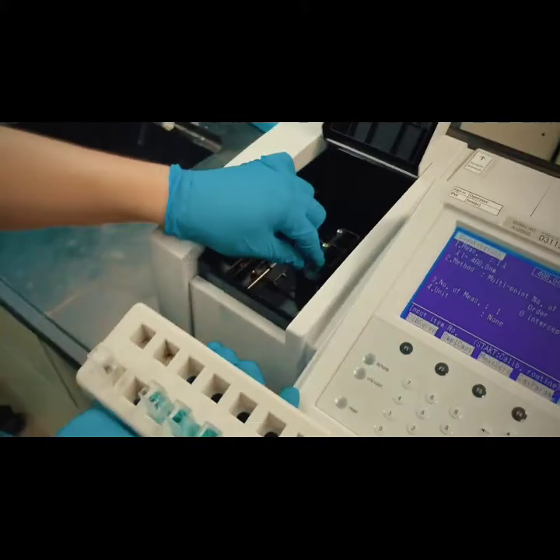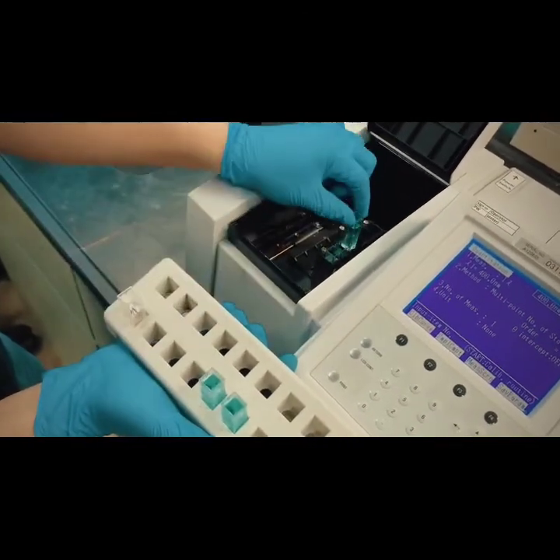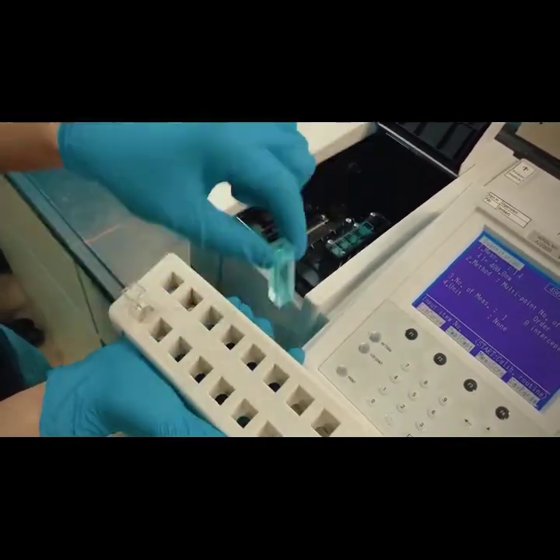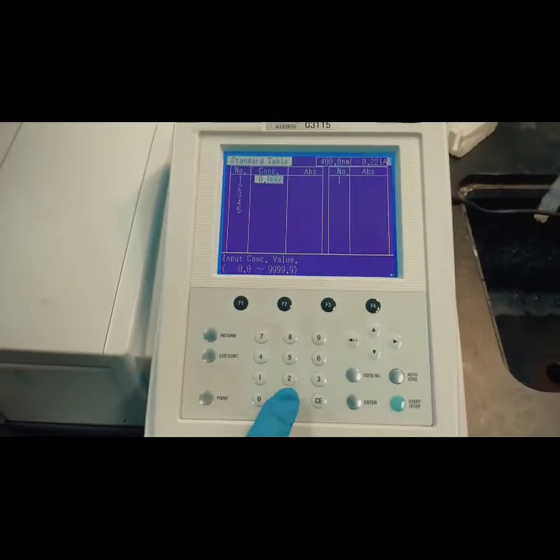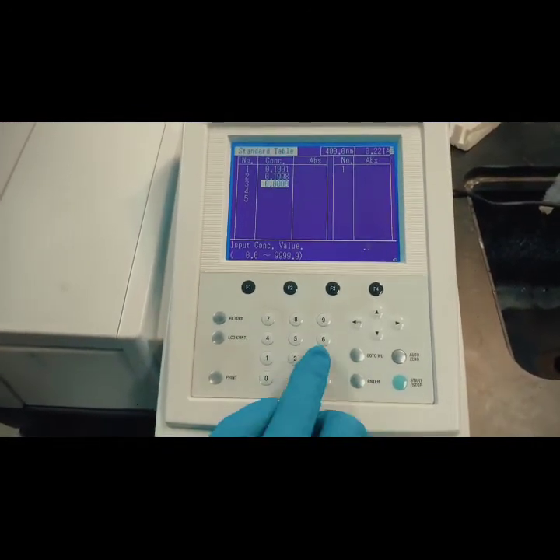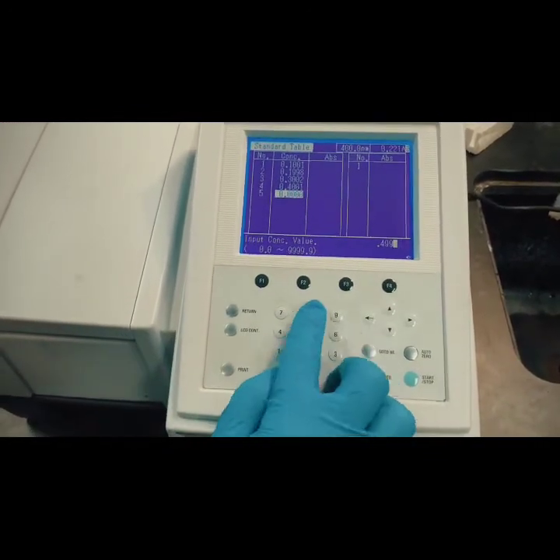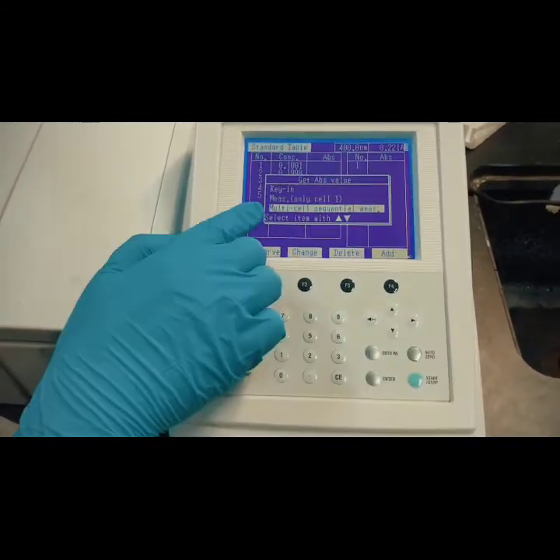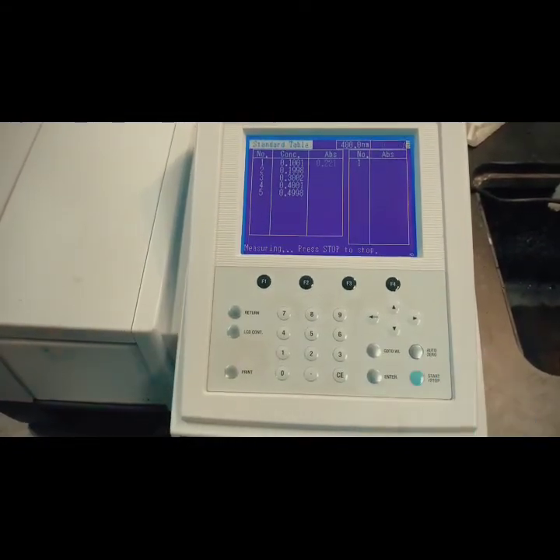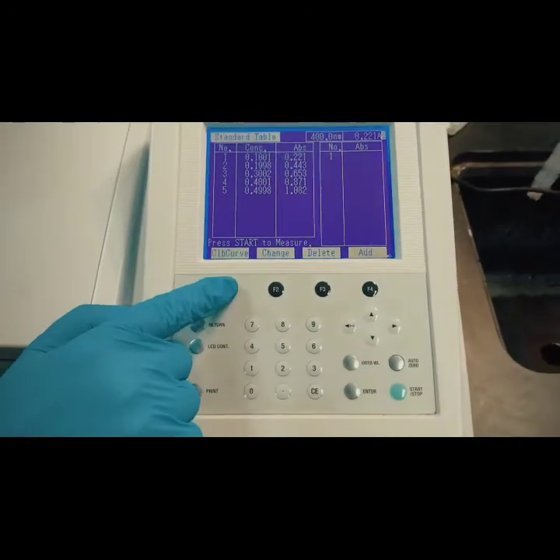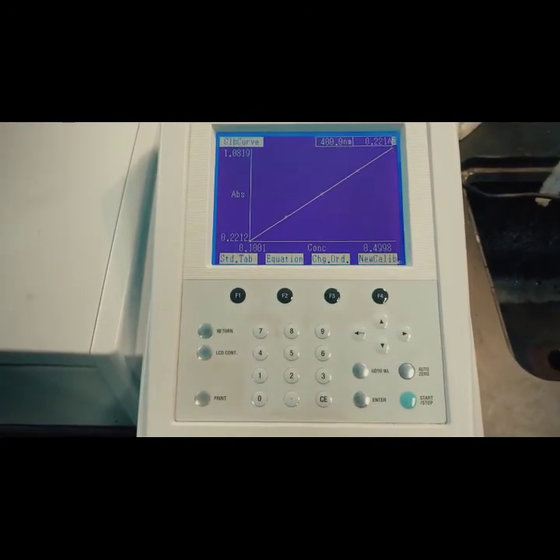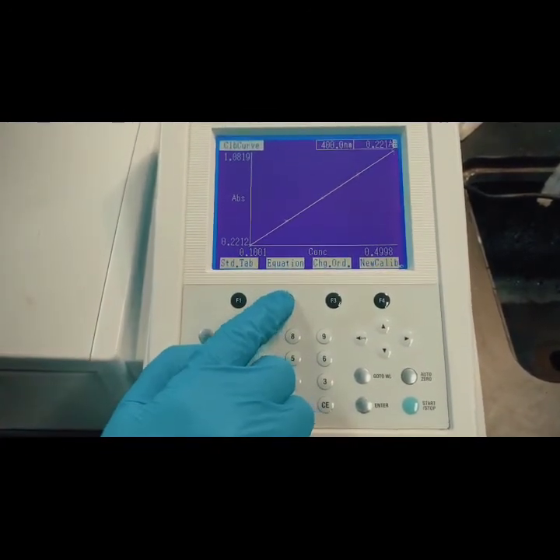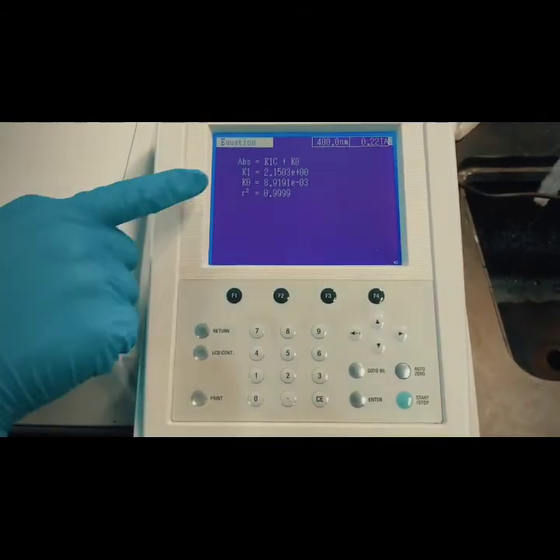When the process is completed, replace the blank cuvette with the prepared cuvettes of standard solutions. Press Start and input the concentration of the solutions for the corresponding cuvettes. Select Multi-Cell Sequential Measurement and press Start. When the analysis is complete, select Calibration Curve to view the graph and Equation to view the equation of the graph.